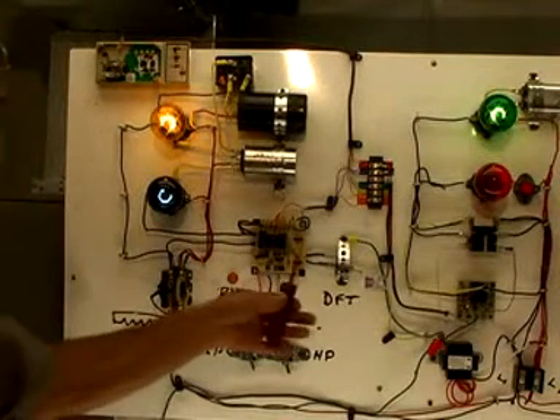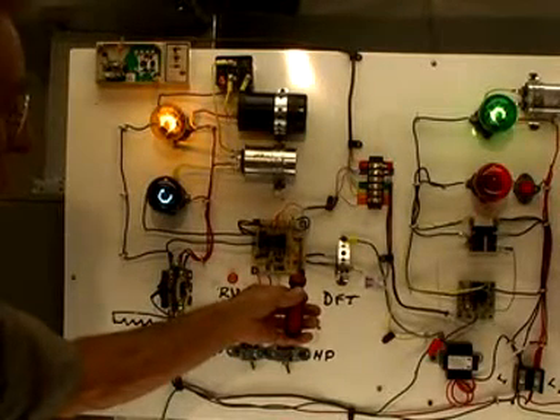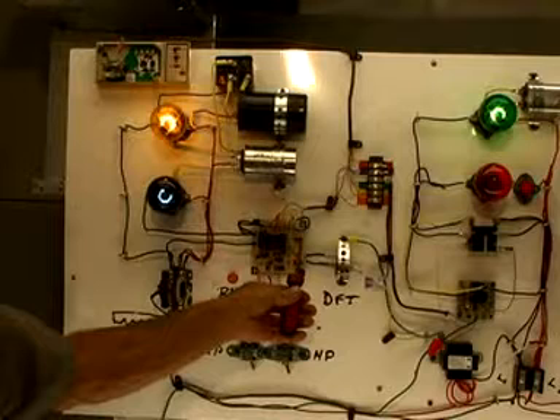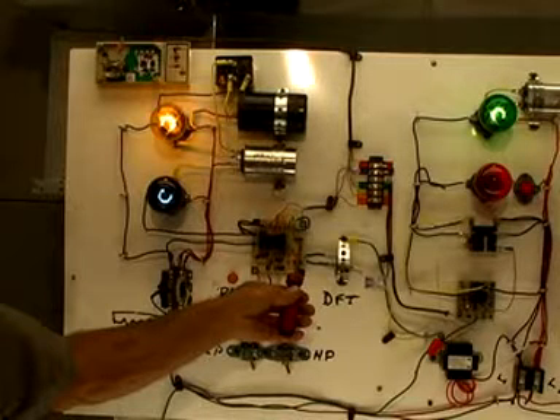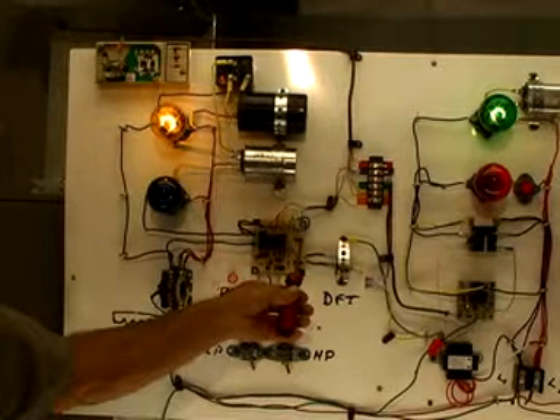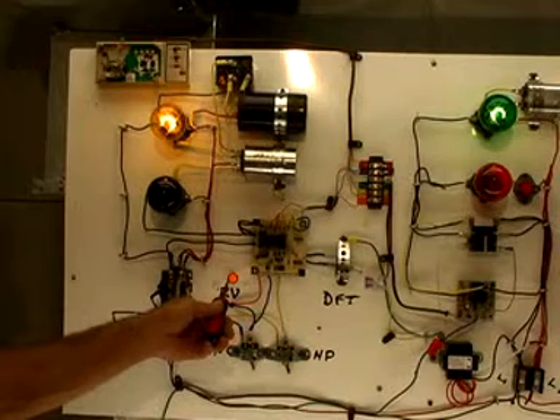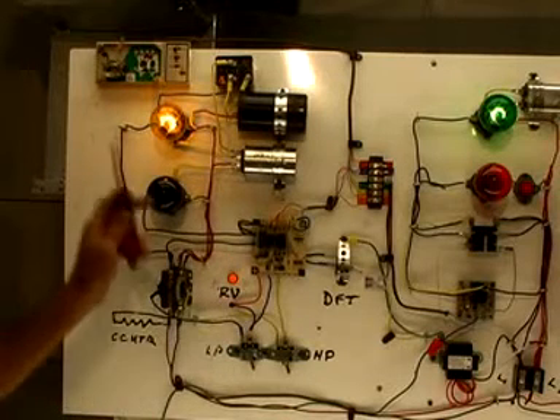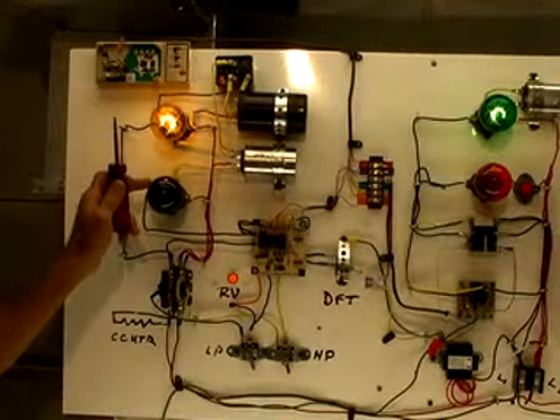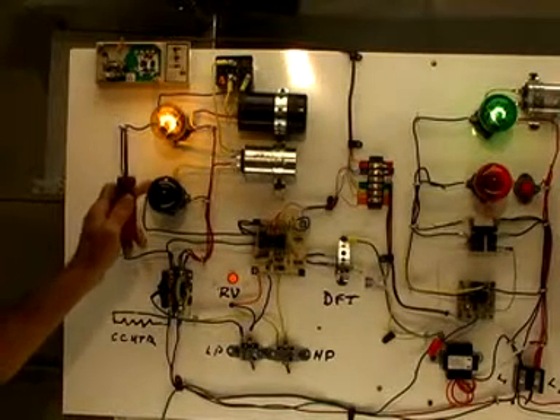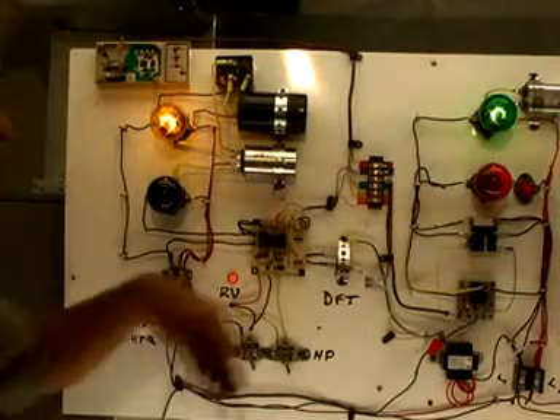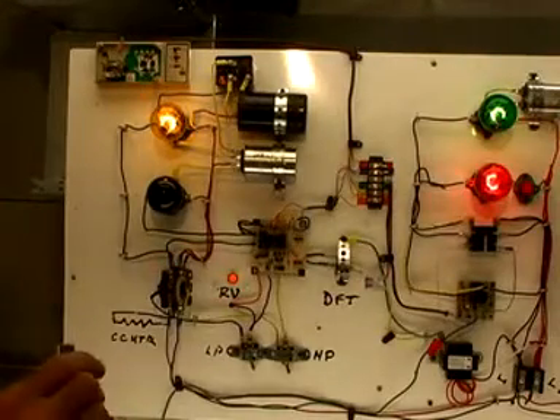So let's do that. I'll get my shorting tool in here. This usually takes six, seven, eight, ten seconds. Okay, the reversing valve is energized, the condenser fan is de-energized, and if we give it just a few more seconds, we'll see the red light come on. Okay, now we're in the defrost cycle.